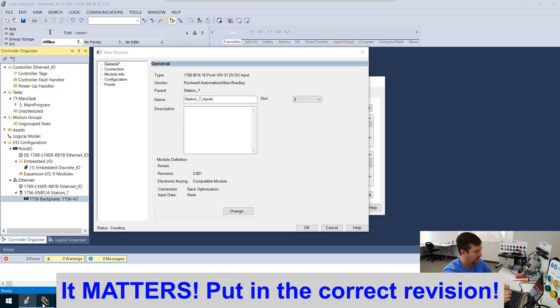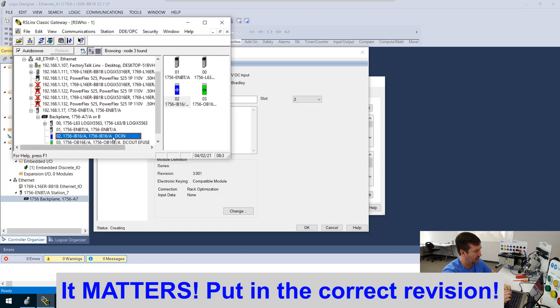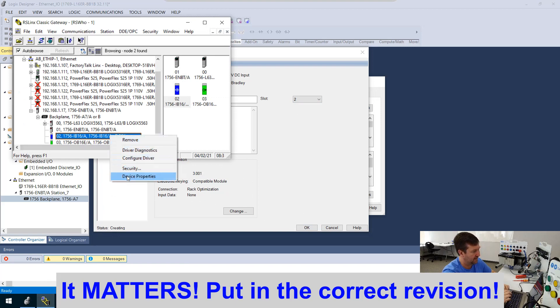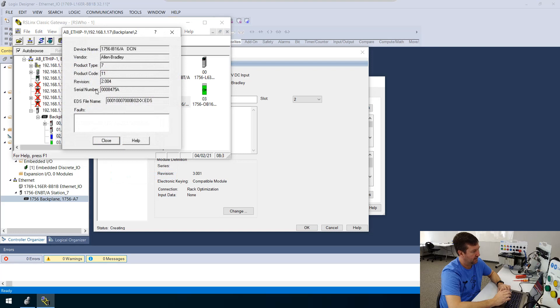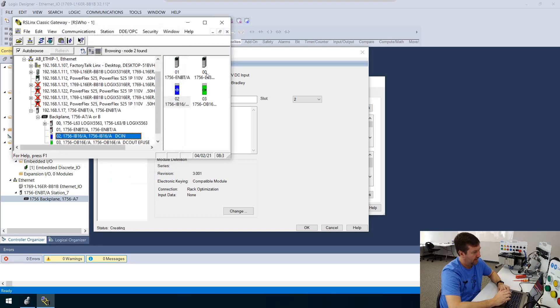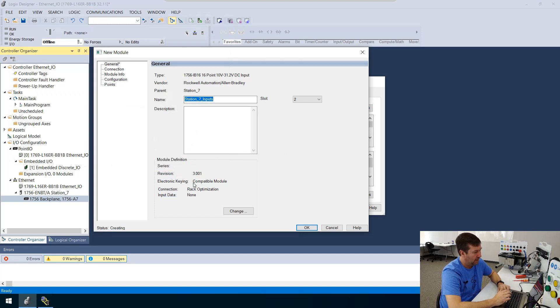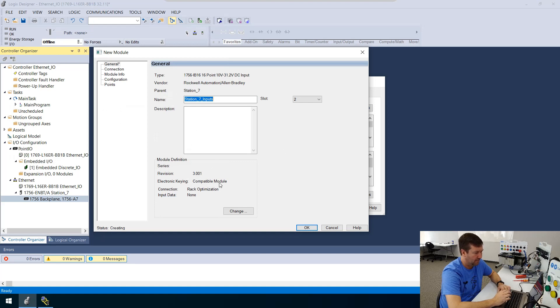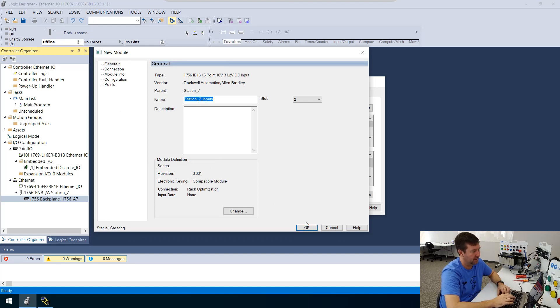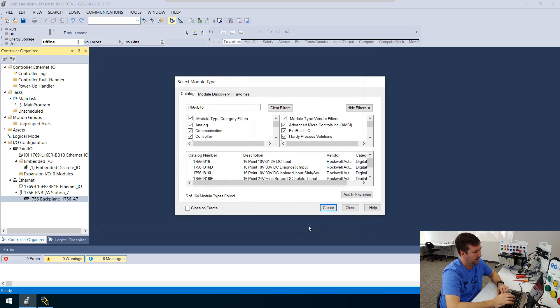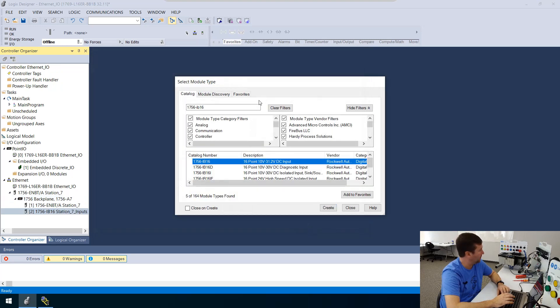And then actually, it shouldn't matter. And we're going to leave this alone. If you notice back here, if I went to properties of that IB16, I've got 2.004. The revision specified here is 3.001. But also electronic keying is compatible module. And I do believe that'll be a compatible module. So we may have to come back and fix this. But let's put okay on that.